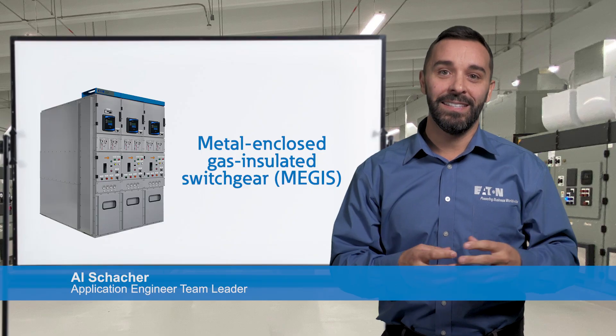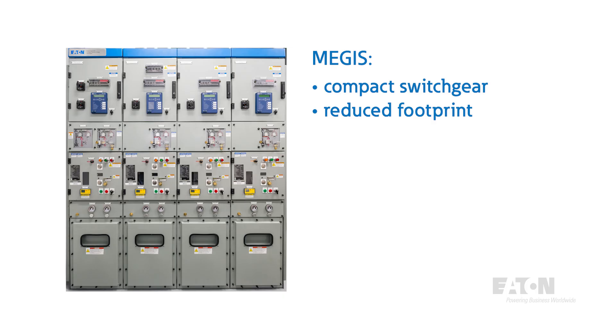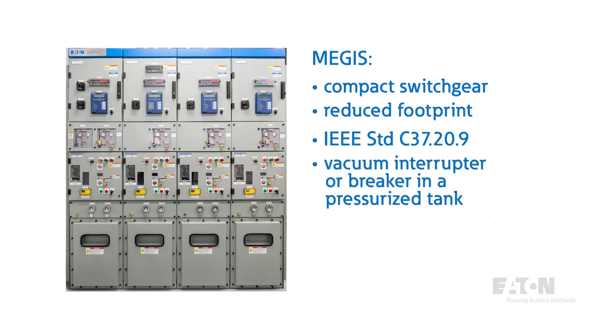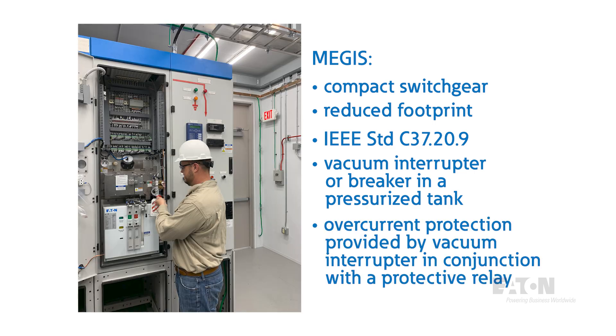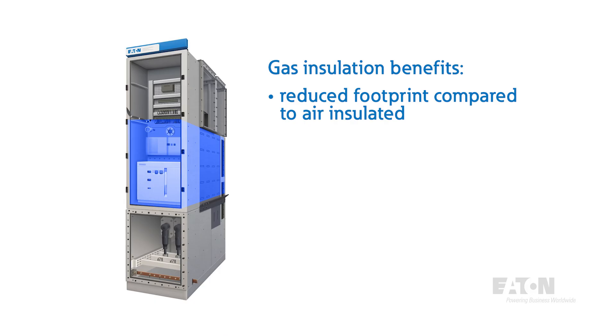Compact switchgear, also known as metal-enclosed gas insulated switchgear or MEGIS, is designed to reduce the footprint of a lineup, especially at the 27 and 38 kV classes. These configurations are built to the IEEE C37.20.9 standard. The construction of MEGIS equipment is a vacuum interrupter or breaker in a sealed pressurized tank. Overcurrent protection is provided by a vacuum interrupter in conjunction with a protective relay, similar to metal-clad switchgear. The gas medium in the tanks acts as an insulator due to its high dielectric strength, allowing for a reduced footprint compared to air insulated switchgear.